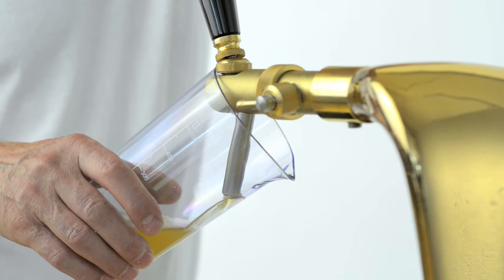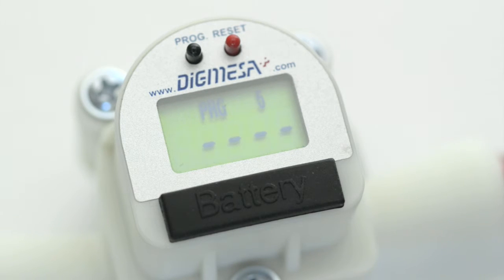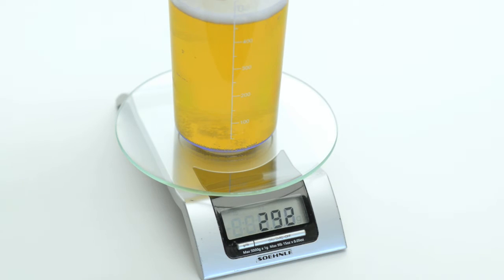Now run about half a liter through the tap into the measuring container. During this procedure, the number of hyphens in the flow sensor display will move from the right to the left-hand side until the flow of liquid is stopped. Place the measuring jar on the scales.